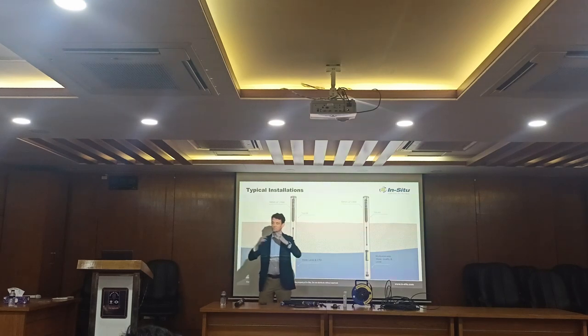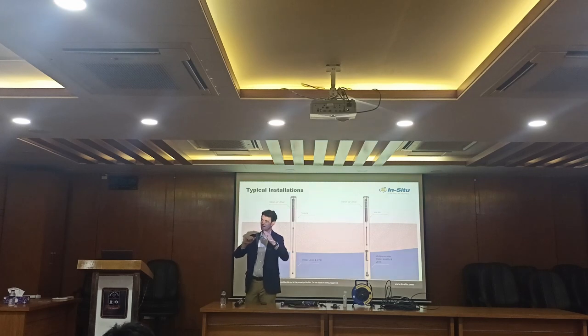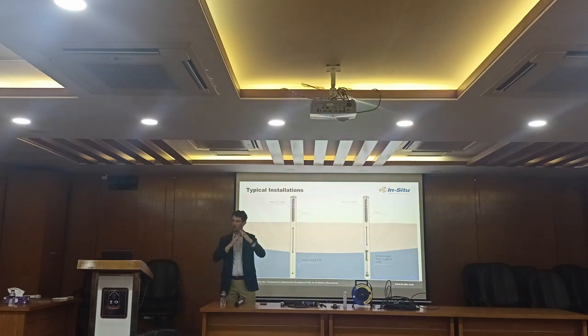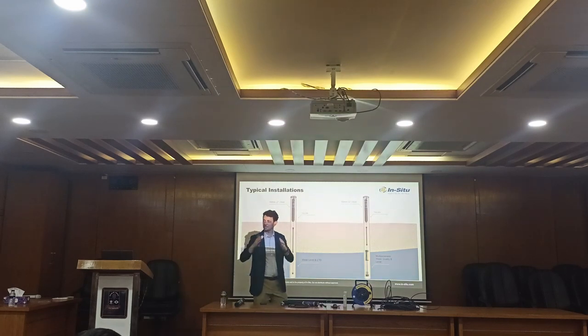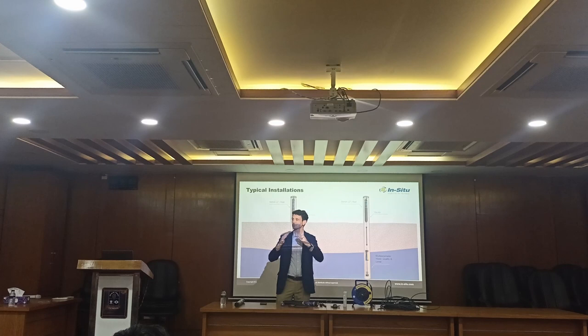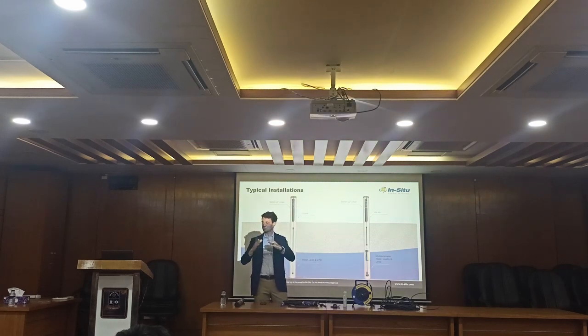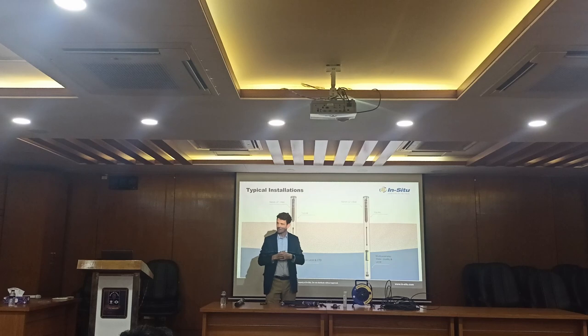What we've done is put a second detector in there that actually measures the LED light coming out, so it knows that it's degraded, and then, using that different detector, it adjusts for that. Based on every single reading, it adjusts, effectively giving you a new calibration every time that light flashes, because it's taking into account that integrated optical compensation.